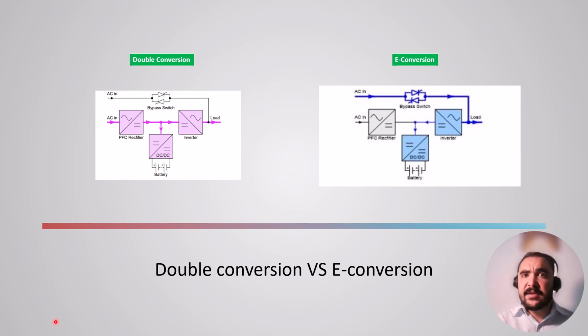At the end of the day, if I paid this much money, I need to make sure the UPS is working perfectly well. So when the UPS reaches the site, I request the engineers responsible for assembly and installation to buy or rent a load bank, and this load bank costs a lot of money. Second, I would need to use real current to check the UPS status under a real load, but this real current will end up on my organization's monthly bill.